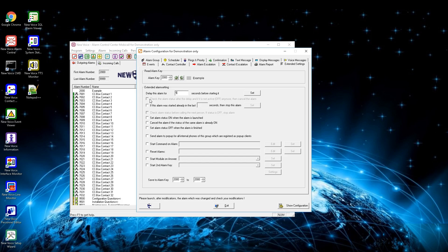This allows the alarm to only launch when the status is on. By activating the next checkbox you can define a time — if the alarm was already launched within that defined time, it won't launch again until the time is over. The next setting is only possible on a sequential alarm: when the alarm status is off, no more persons will be called and the alarm will be cancelled. Activate the next checkbox to set the status of the alarm to on when it gets launched. With the next checkbox the alarm won't launch again as long as it has its status set to on. The next checkbox is to send the alarm as a pop-up to all internal phones from this group — the devices need to be registered as pop-up clients. By activating the next box you can define a command to be started at alarm start — this can be any Windows command or MobiCall command.